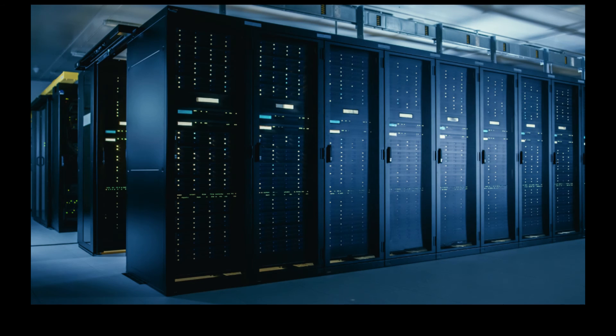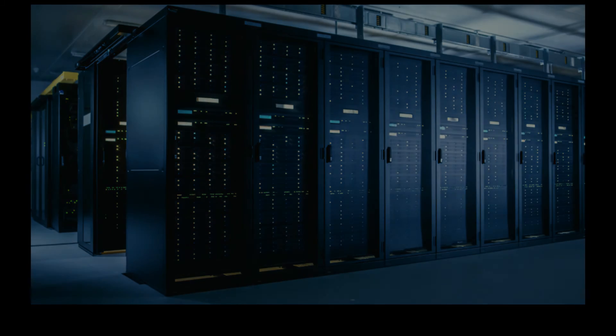If you're in a data center with very long rows, consider running everything within one row to the center of that row and placing your power and ground bars there.